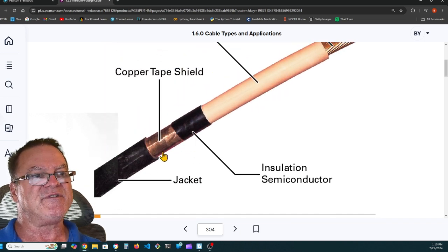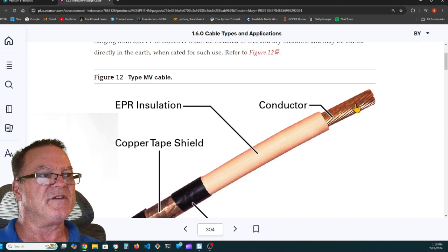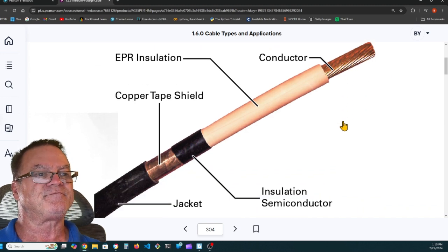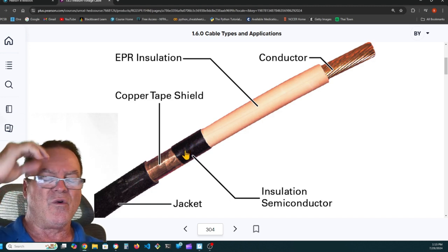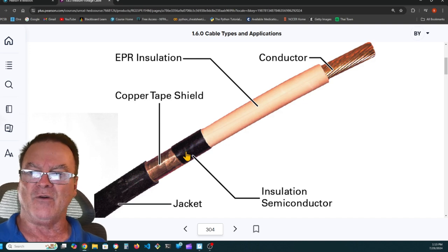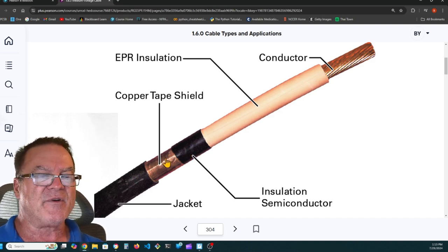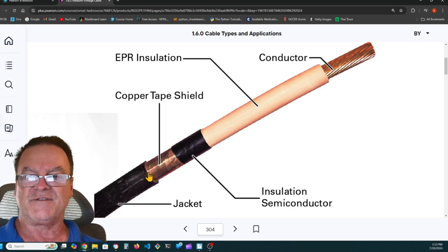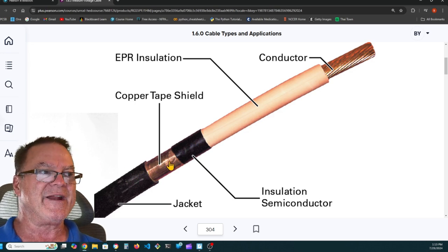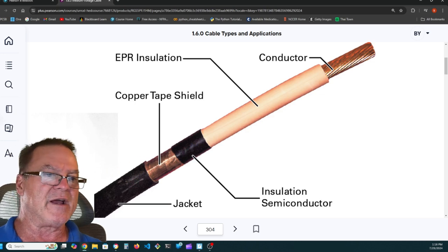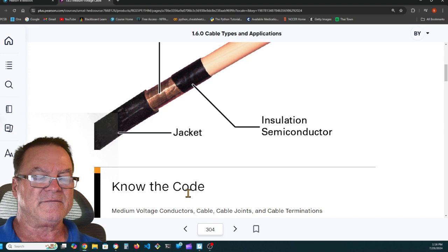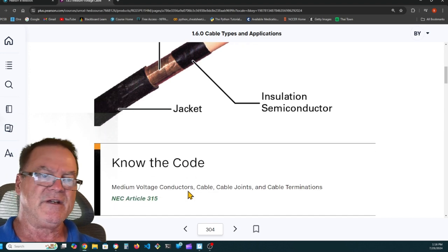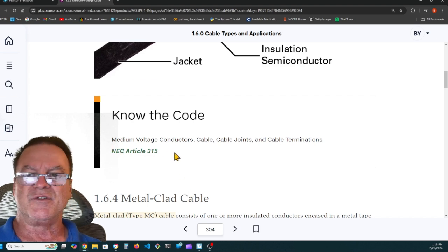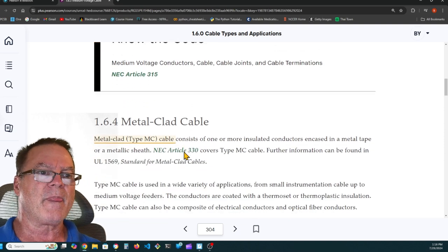So here's the jacket. Here's a copper tape shield, and it has an insulation semiconductor. Then here's the EPR insulation, and then there's finally the copper conductor itself. This insulating semiconductor helps with stray voltages or helps with the accumulation of static voltage on the insulation of the conductor. And this copper tape shield will take any of the buildup of static electricity to ground. When you're terminating this type of cable, you take the copper tape shield and it's taken to ground. And it keeps it from blowing out the cable in other places. It bleeds off that excess induced voltage in the cable jacket. It takes it to ground.